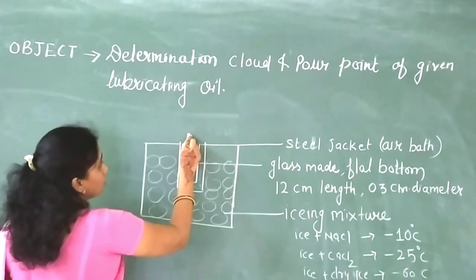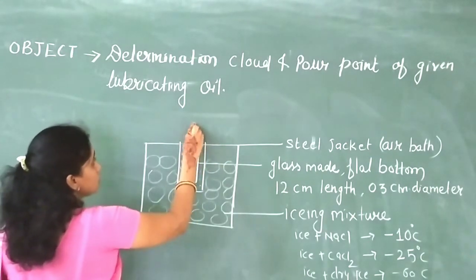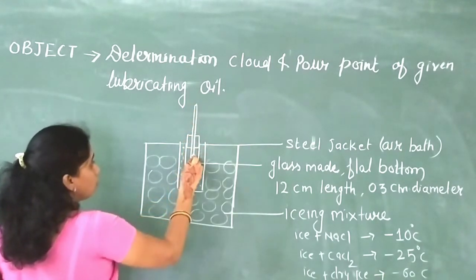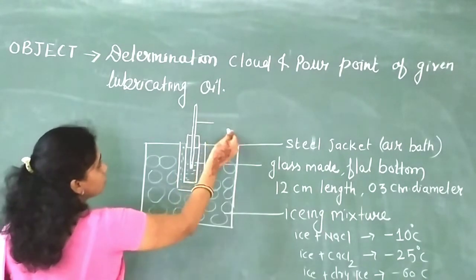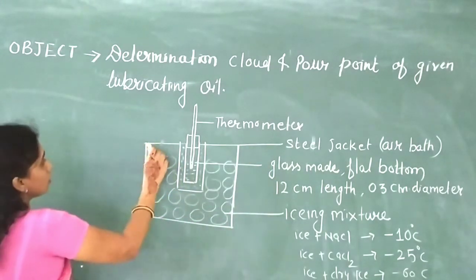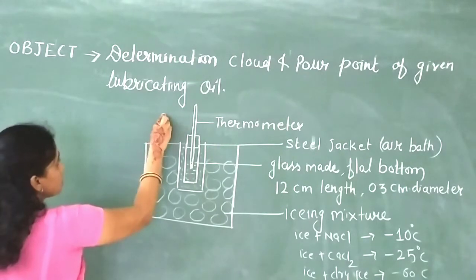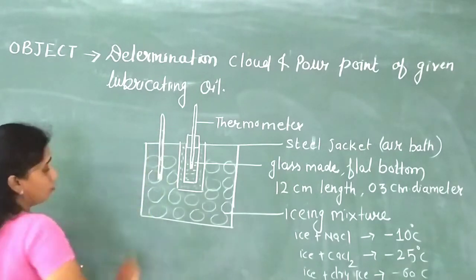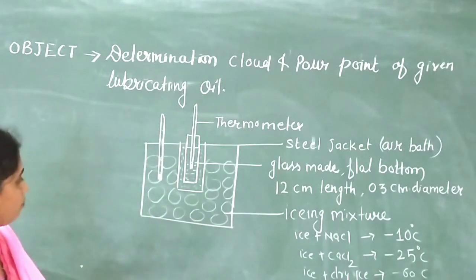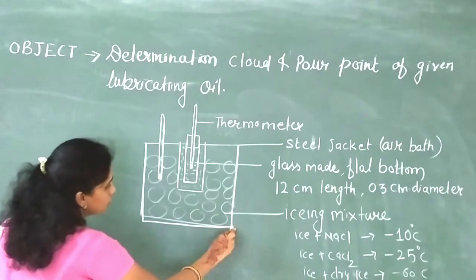The test jar has a single-hole cork, and through this hole we insert a thermometer to measure the temperature of the oil. One more thermometer is also immersed in the icing mixture so we can measure the temperature of the icing mixture.